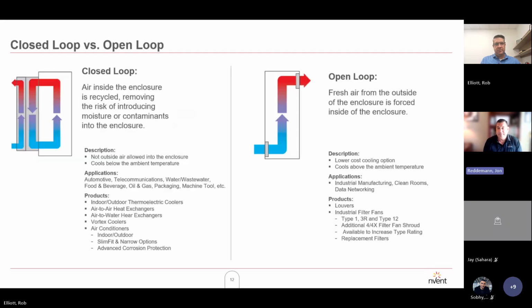Next slide, please. So we kind of talked about this, closed loop versus open loop, where we're just recycling enclosure air. We don't have any interaction. And then open loop is essentially using the cooler air as our cooling medium to manage our overall heat loads. And that 10 degrees is the general rule of thumb.